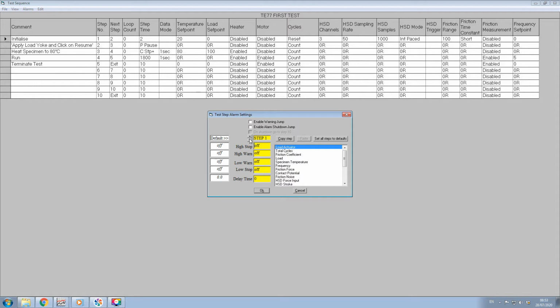It is important to note that when a new test is created, no alarms are set. When creating a new test, it is important to set alarms suitable for the test parameters, or as an absolute minimum, use the Set All Steps to Default option to ensure that the test parameters do not exceed the machine's capabilities. Alarms may be set for each step in the test and for each required parameter, although it is usually only necessary to set alarms on the most important parameters, for example, load, temperature and friction.